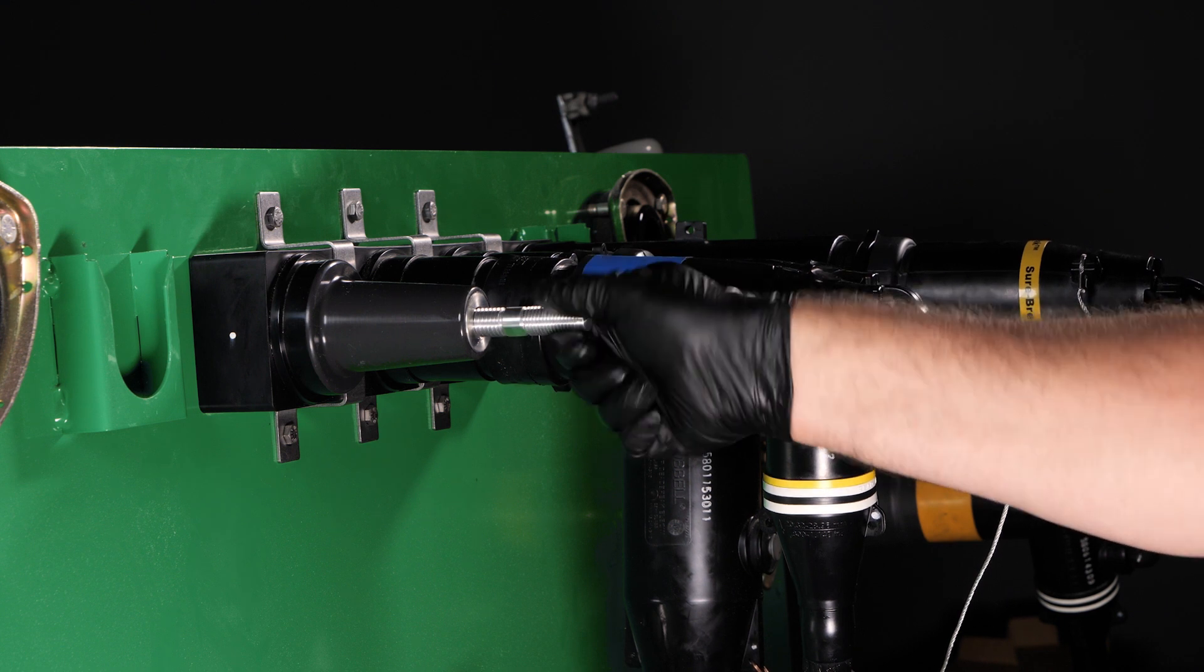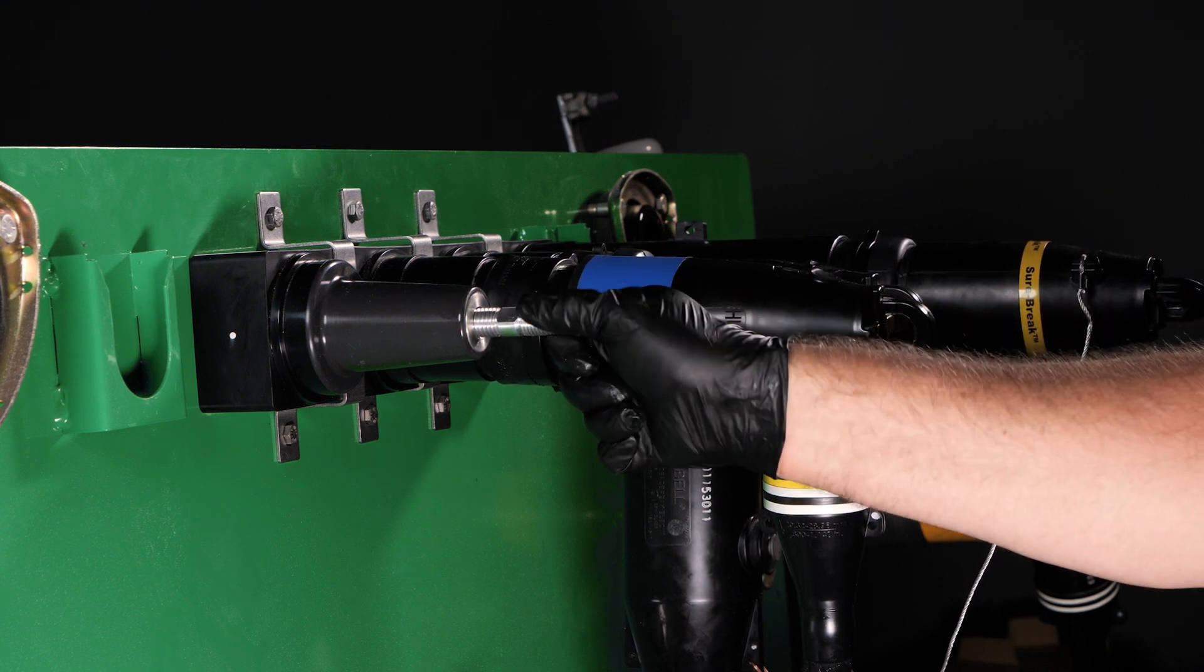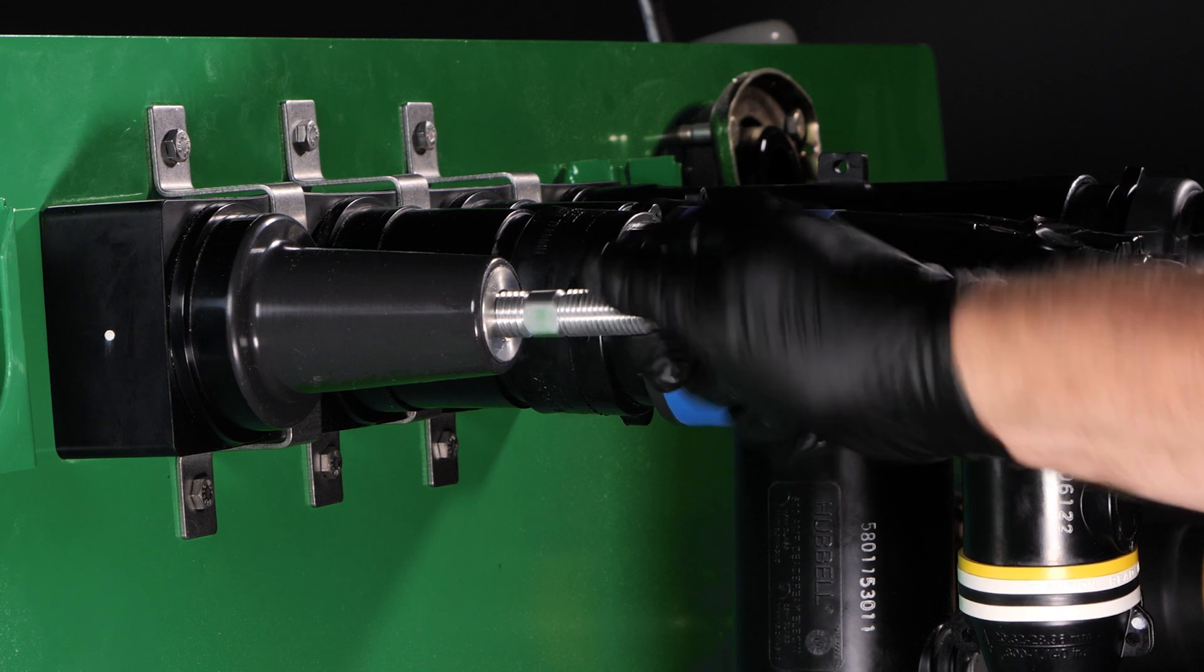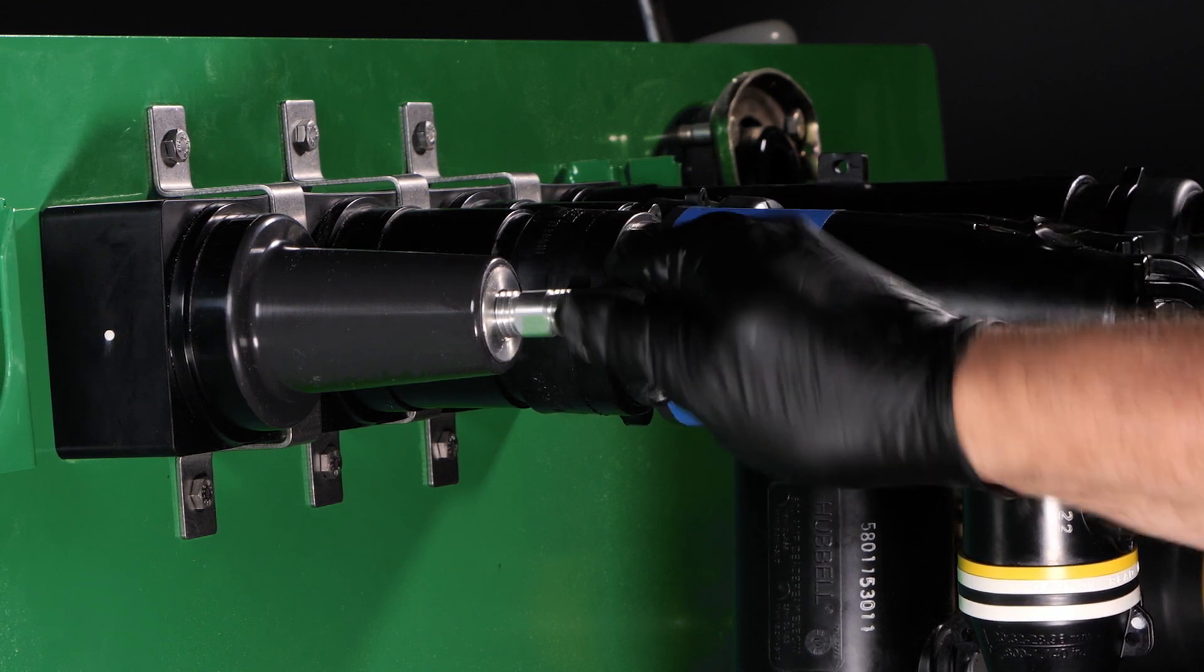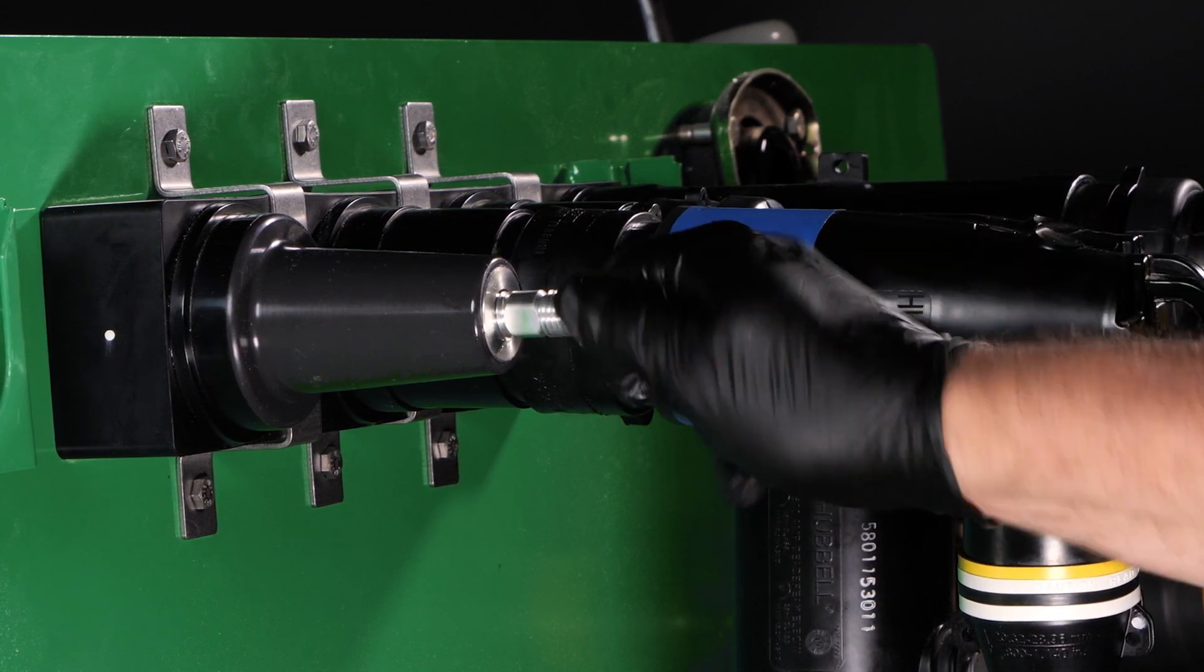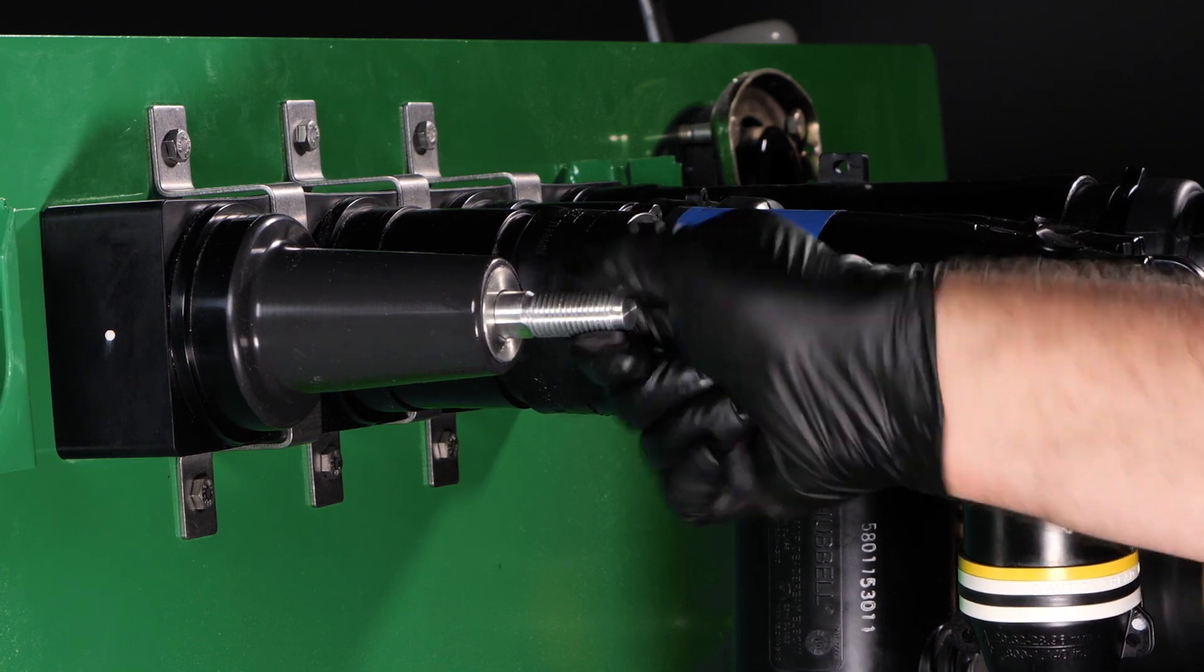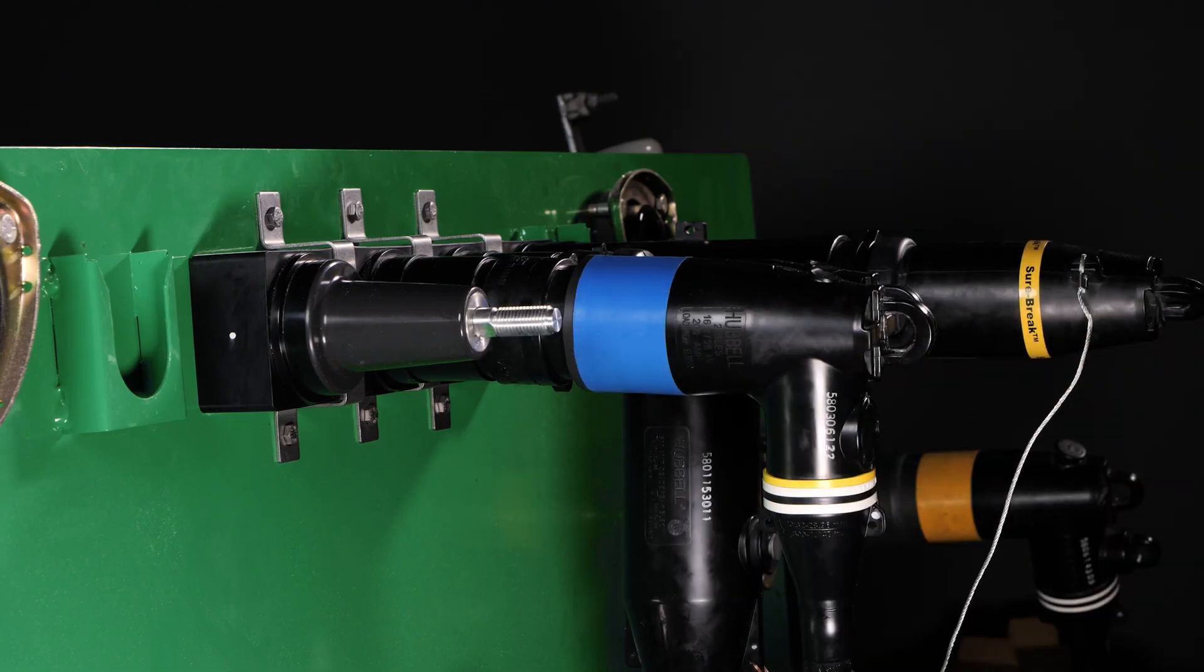The end of the stud with the shortest threads screws into the equipment bushing and the longest side threads into the SureTap. The stud should easily thread into the equipment bushing. If it does not, then simply reverse the orientation of the stud so the short side installs into the bushing.